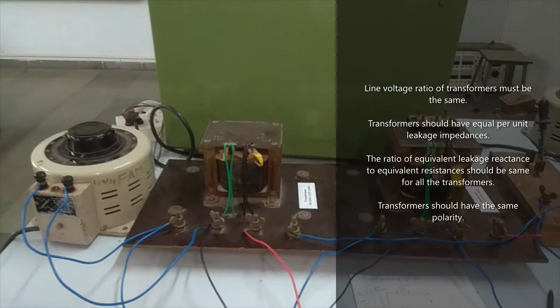That is, if the secondary is connected wrongly with wrong polarity, there will be a large circulating current which will flow through the transformer and it may damage it. So considering this important condition...